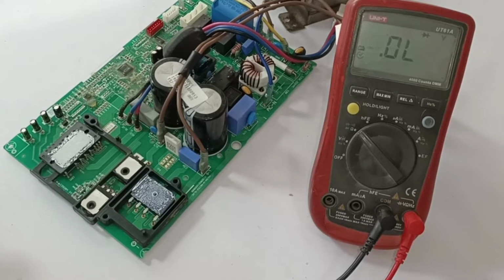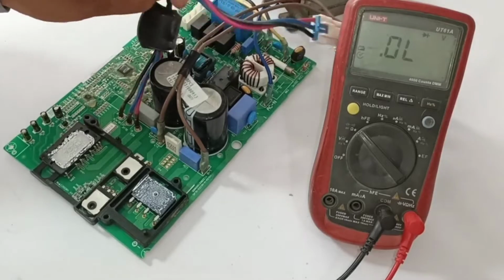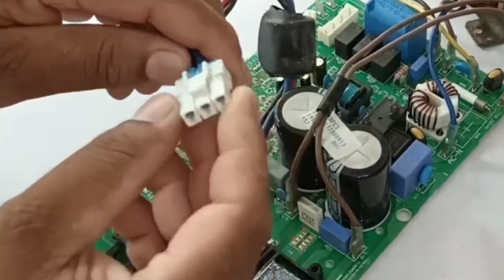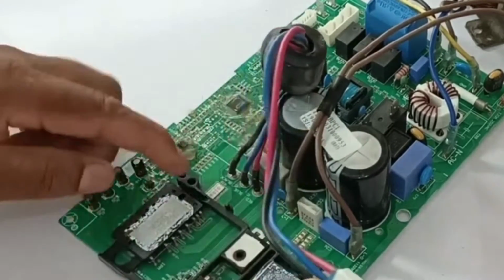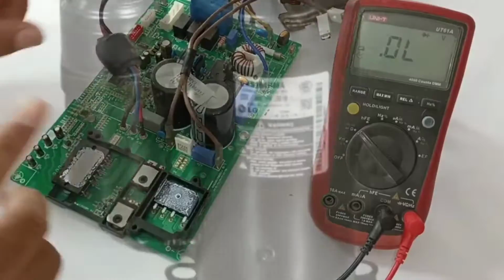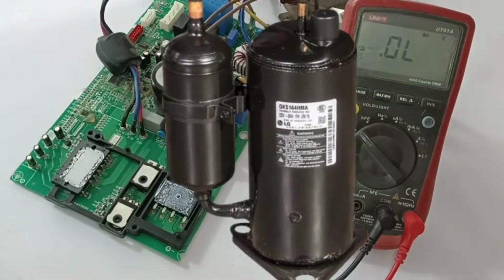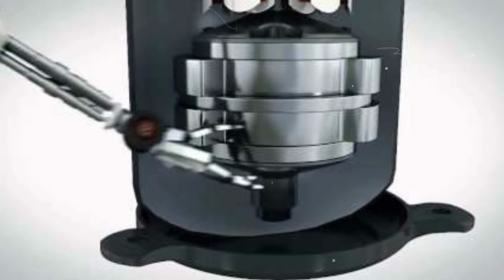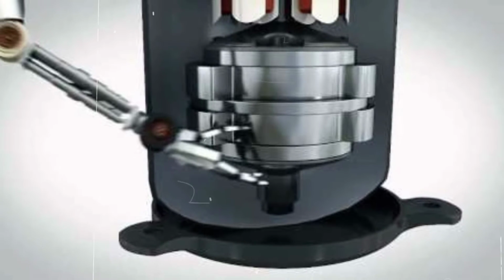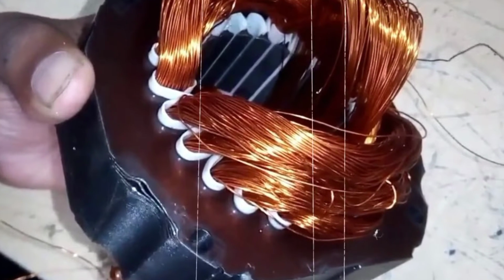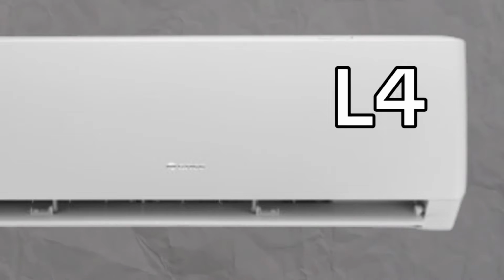Before testing the circuit board further, if, for any reason, the wire attached to the compressor is disconnected, the circuit board will still show the L4 error code. Besides this, the compressor itself may be bad, that is when the compressor pump mechanically goes bad or if its winding electrically short circuits. Still, the L4 error will be shown.